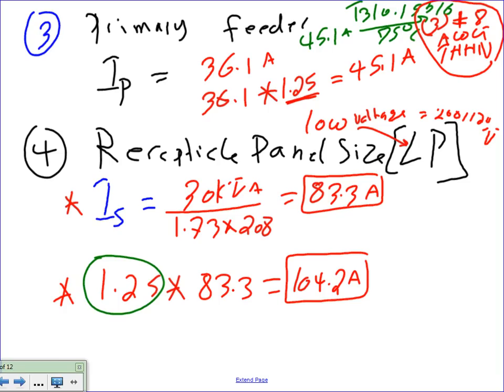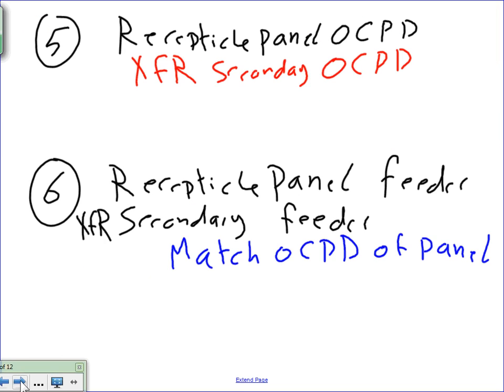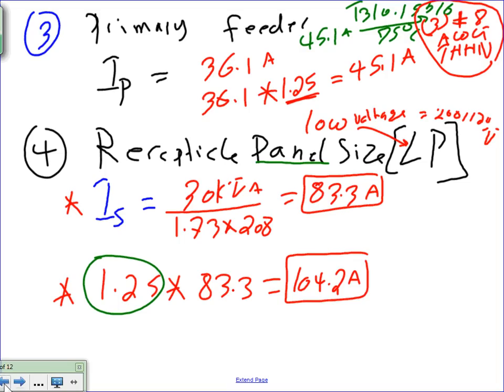Okay? Then, the last one, guys, remember, we are sizing a panel. We're not sizing an overcurrent protection device. We're sizing a panel. So if you guys go to, did I do it in the second slide? No, I did not. I used it right here. So right here, you're going to take the 104, step number 3.2, Oladipo, take it to the code. What was the code that talks about panels? The one that talks about 312. Thank you. 3-12 or 3-13, depending how high you go.